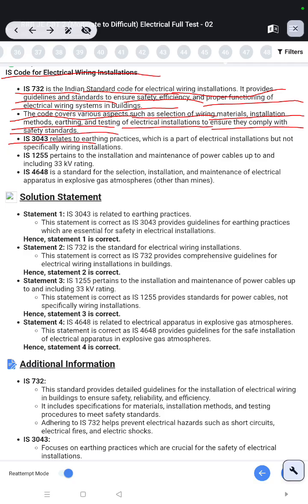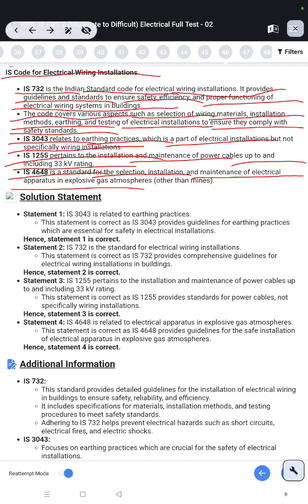IS 3043 relates to earthing practices, which is a part of electrical installation but not specifically wiring installation. IS 1255 pertains to installation and maintenance of power cables up to and including 33 kilovolt rating. IS 4648 is the standard for the selection, installation and maintenance of electrical apparatus in explosive gas atmosphere other than mines.